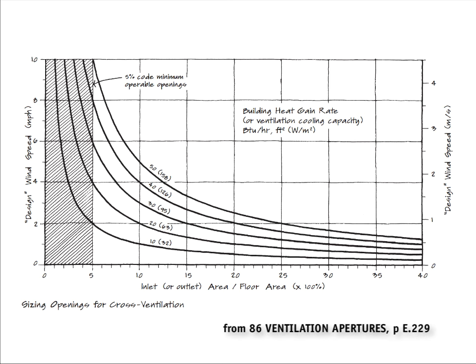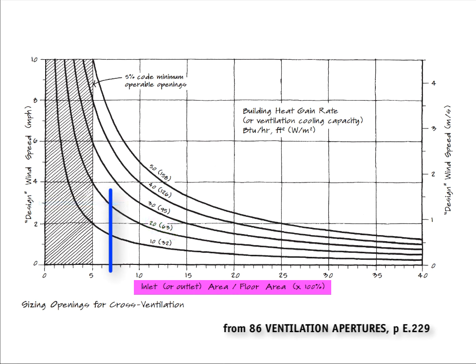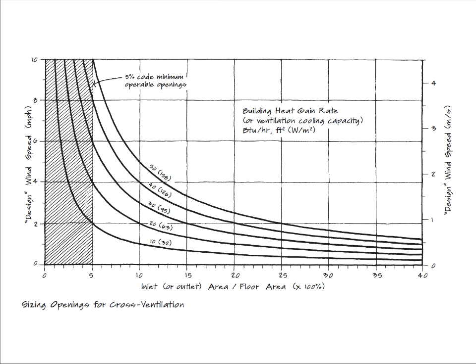Once you know the design wind speed, enter it on the vertical axis, travel horizontally until you meet the curve for the building heat gain rate, then drop down to find the inlet or outlet area as a ratio of floor area. For instance, 10% means 10% of the floor area in inlets and another 10% in outlets. Multiply that ratio by the floor area to find the actual inlet or outlet area. Remember that outlets need to be at least as large as the inlets.